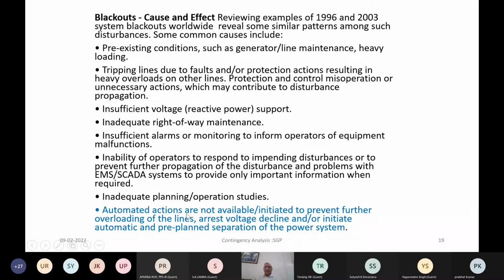Of course, inadequate planning and operation studies and lack of automatic actions is basically one of the reasons, because it has been seen that in system disturbance, manual intervention from the operation engineer is sometimes not possible, humanly not possible, because the time required to take a corrective action in a manual way is not sufficient. So automatic schemes are necessary in such cases.